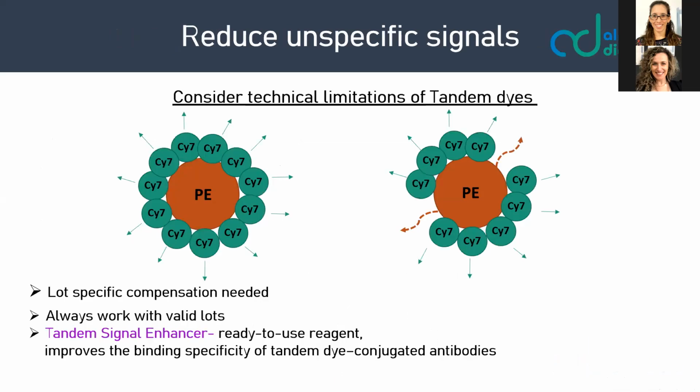So one thing that needs to be considered also when performing compensation and performing multicolor panels, you should consider the technical limitations of the tandem dyes. Tandem dyes can actually break apart if they are not valid anymore. I mean, we need to pay attention to the shelf life.